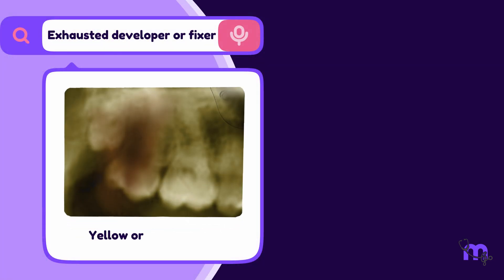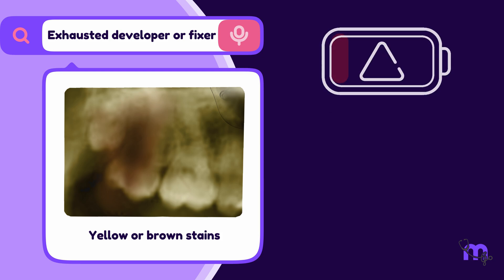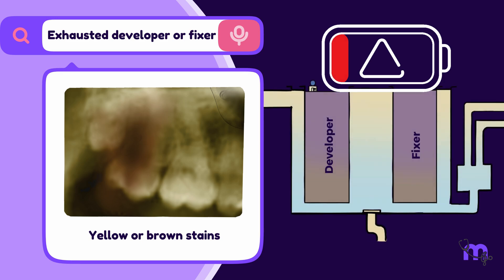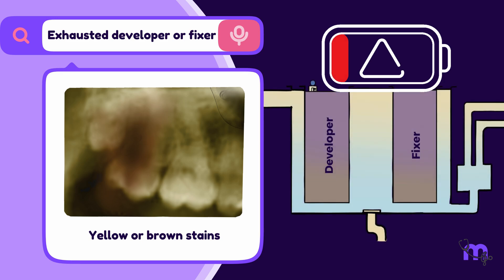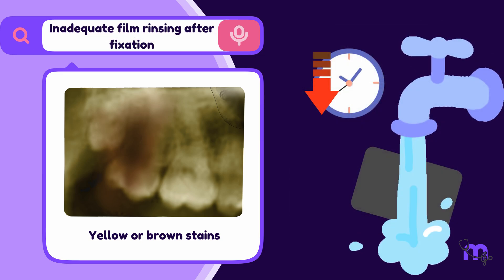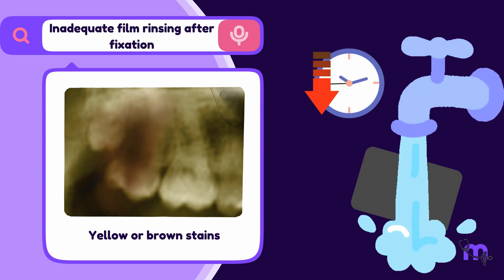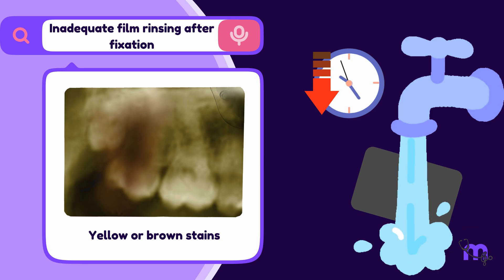Yellow or brown stain on the film is another common error. These stains arise from two main causes: using an exhausted developer or fixer, and not rinsing the film thoroughly after removing it from the fixer.